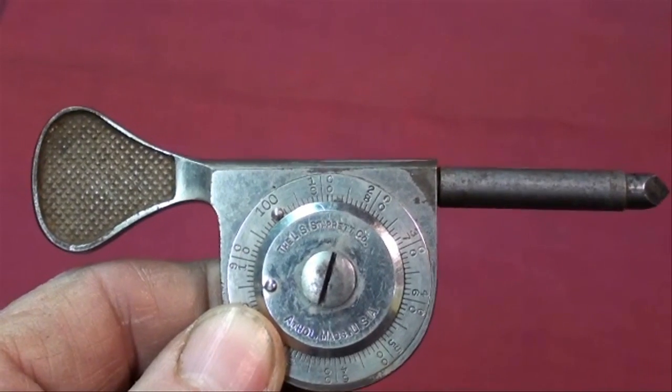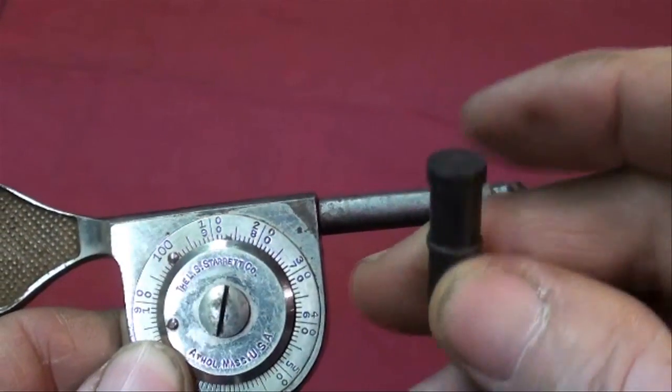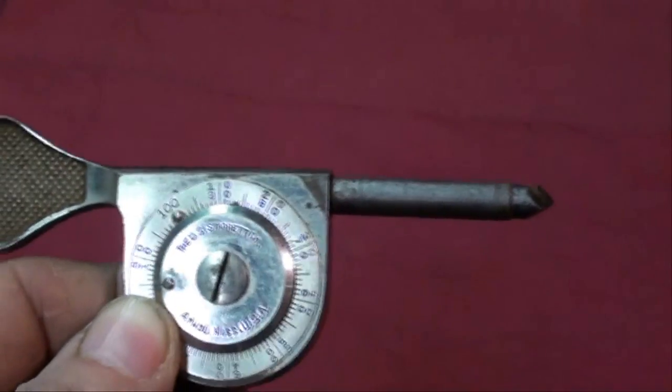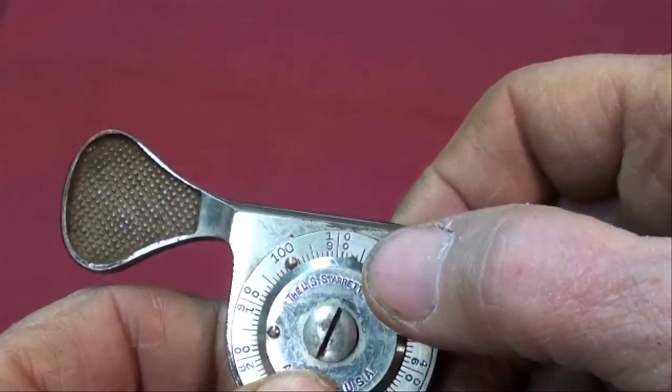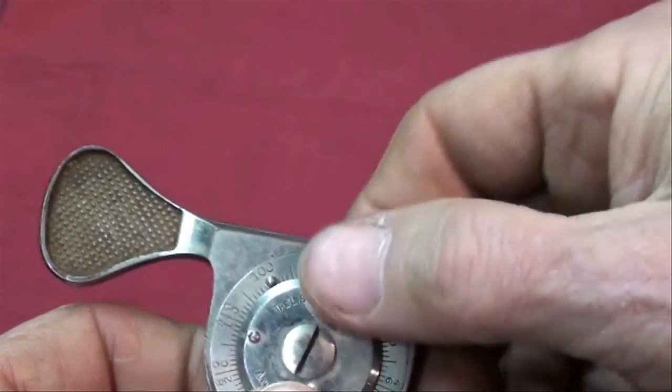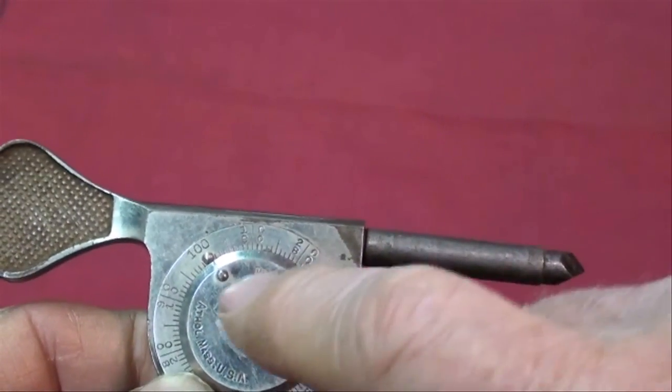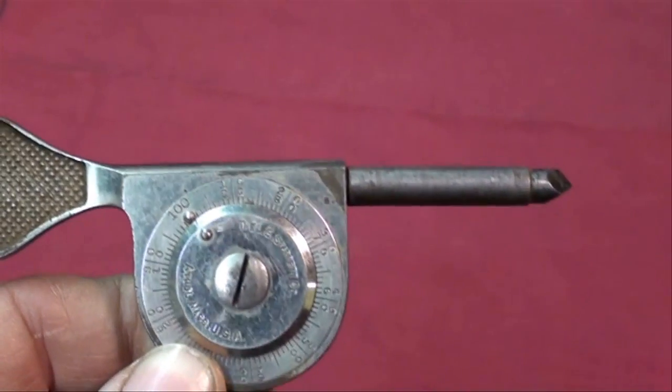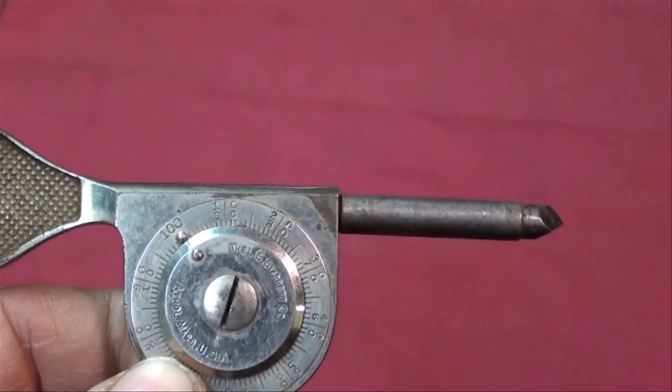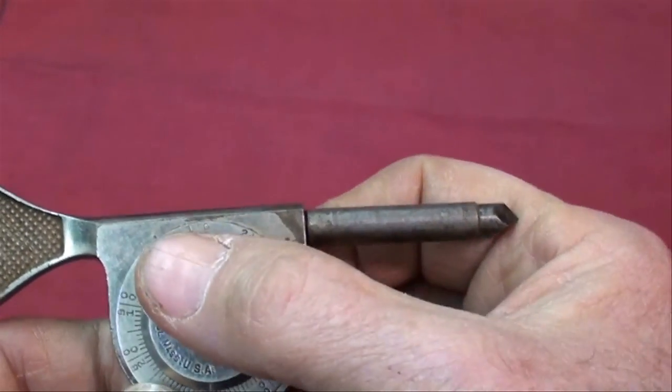I think I'll use the Starrett speed counter next. The speed counter comes with several different tips. This particular one you can set it to zero. There's a worm and a worm gear in here, so I'm going to set it to zero, and then each full revolution is 100 rpm. The reason for these little buttons here is that in the olden days, men were often checking the speed of line shafts and other things above their head, and they could feel the little bump come around with their thumb and count that way.